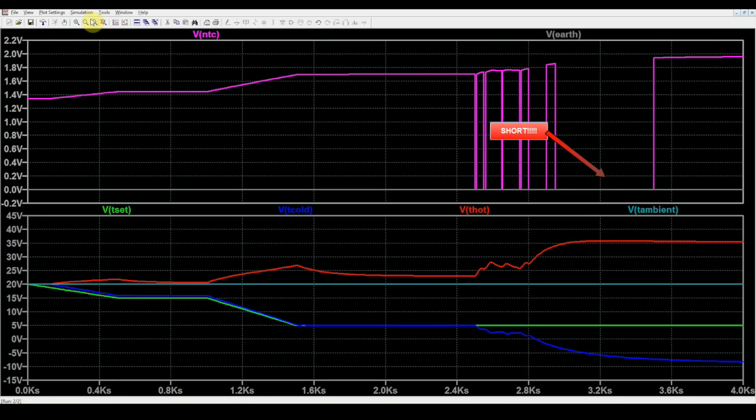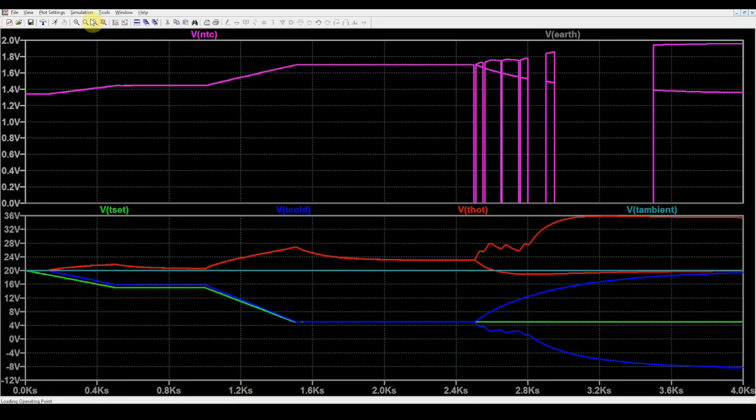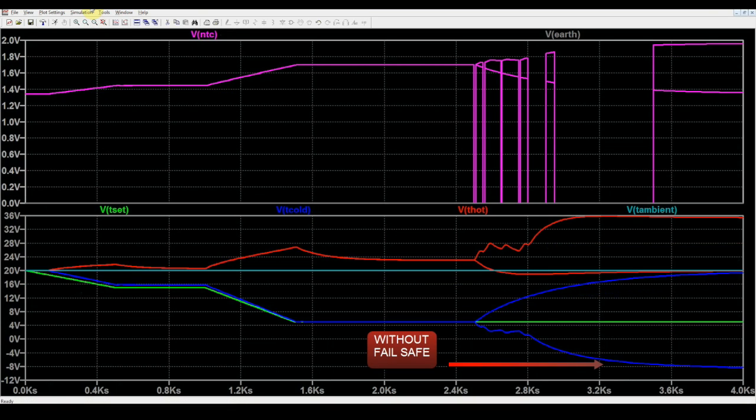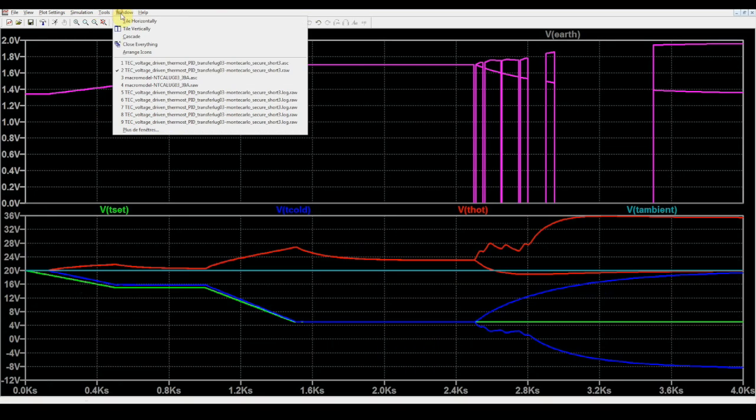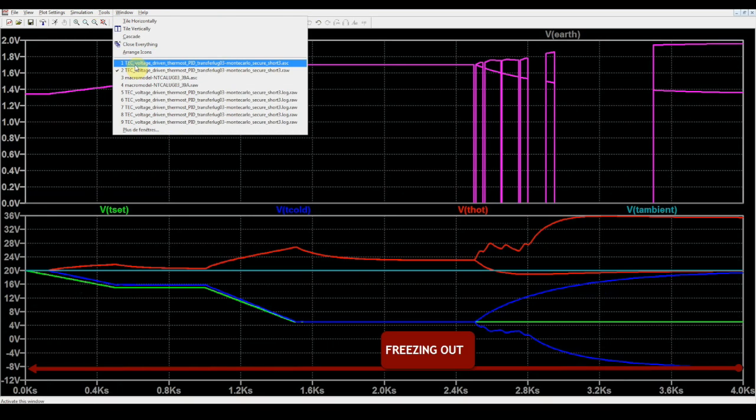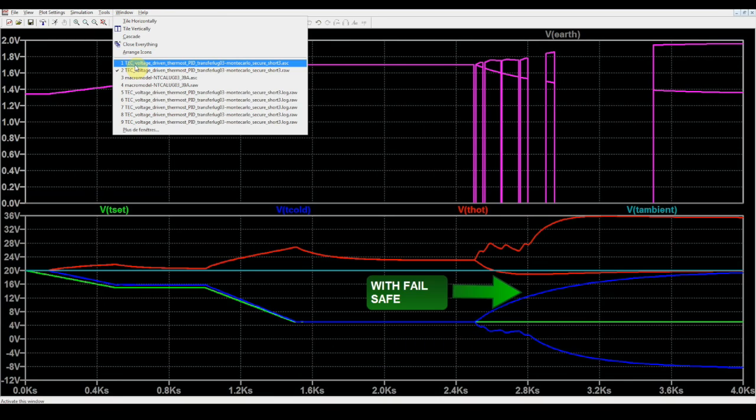The two simulations are done one after the other without and then with fail-safe. Without fail-safe, the cold temperature is driven to much lower temperature than 5 degrees C, as the PID sees a high temperature on the sensor, eventually leading to a complete freezing of the device.